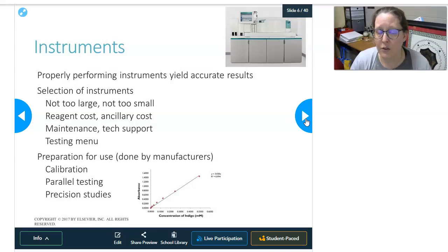You need to do precision studies also. Again, often that's done by the person that comes and installs it. Precision studies is where you run the same sample over and over on a specific test, and if it's one test on one sample, you should get the same result over and over. So how often are you getting the same result, or are results varying every time you run it? If the results are varying every time, then you might have some precision issues. You can also do that by running several in a row, running water in between to see if you're getting a true zero, if there's some carryover. There's all kinds of stuff that has to be done to make sure that everything is ready to go and you can turn out quality results.